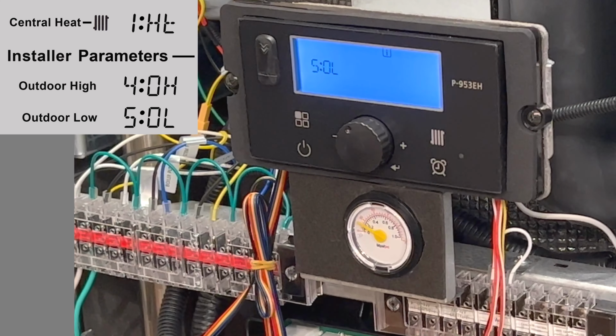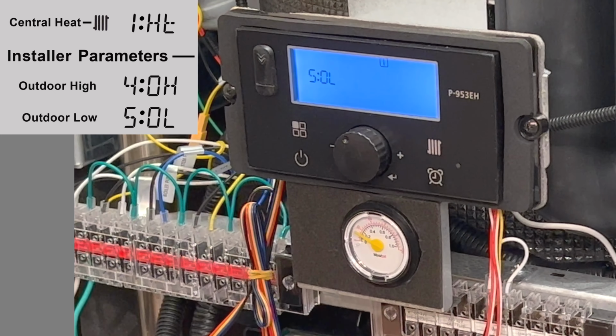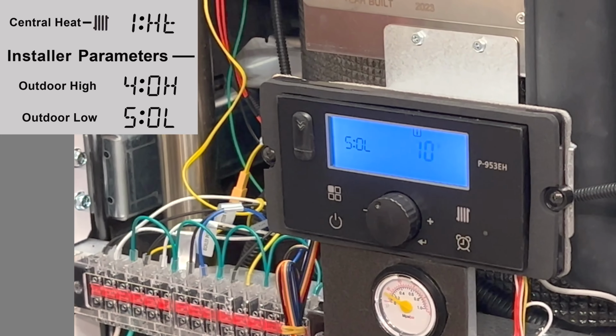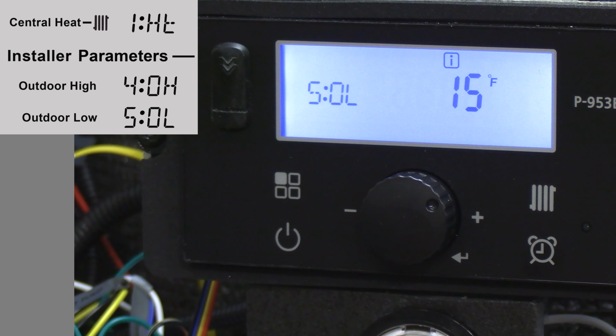However, if you have an older dwelling that doesn't have a lot of insulation or some drafty windows, you might want to bring that up a little bit. So in this example, I'll say at 15 degrees of outdoor air, we're going to deliver the 180 degrees. And I'm going to store that, I'll press the scroll select button.